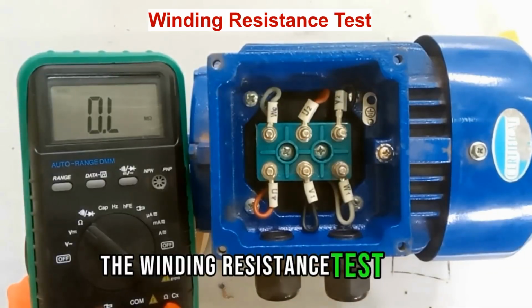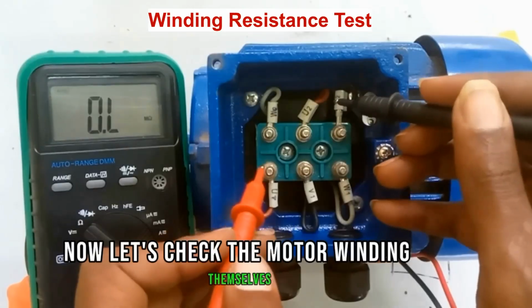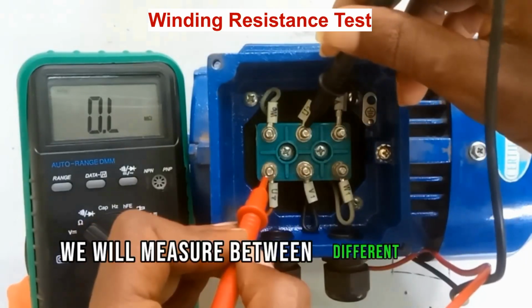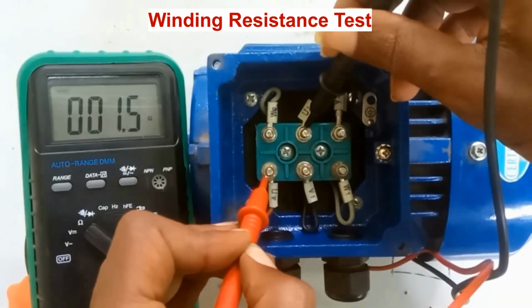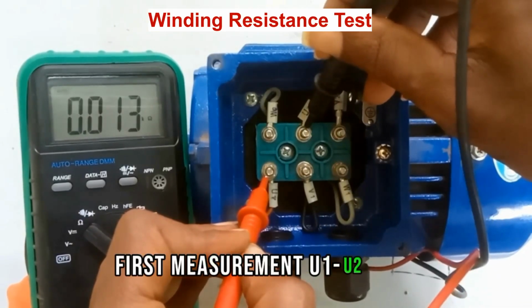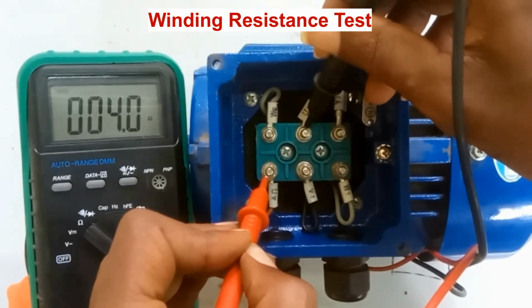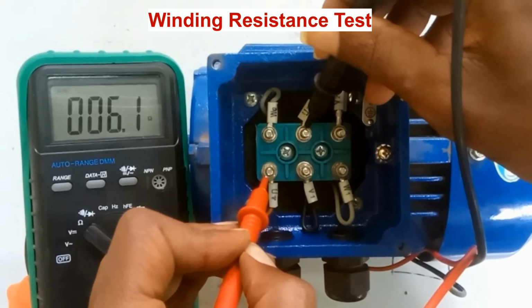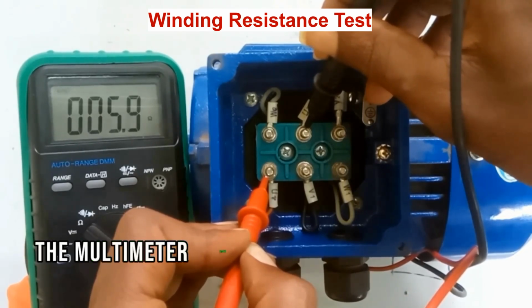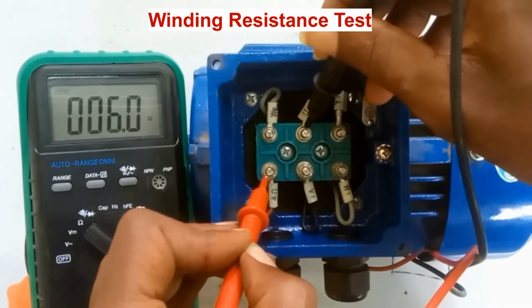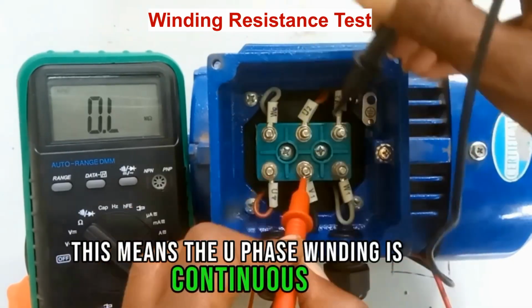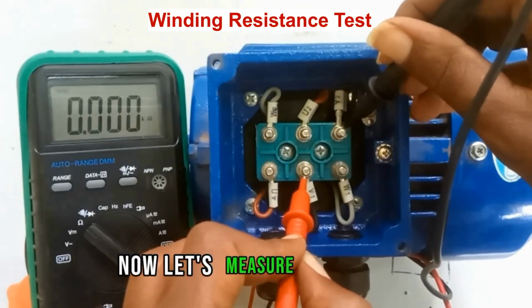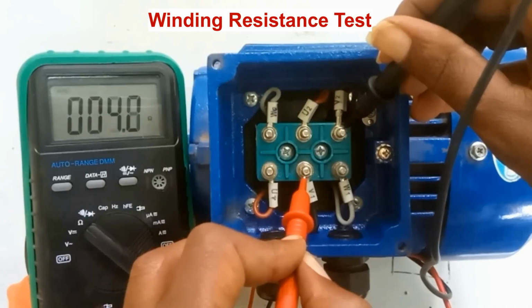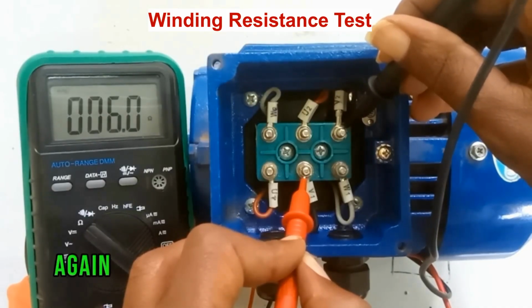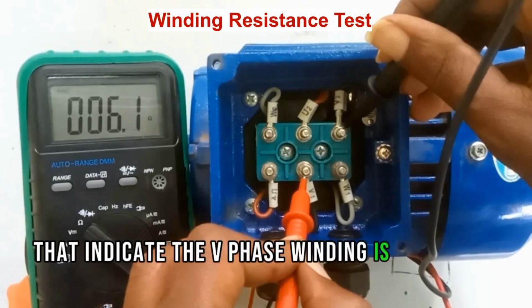The winding resistance test. Now let's check the motor windings themselves. We will measure between different terminal combinations. First measurement, U1 to U2. The multimeter reads approximately 5.9 ohms. This means the U phase winding is continuous. Now let's measure V1 to V2. Again, we get approximately 5.9 ohms. That indicates the V phase winding is also healthy.